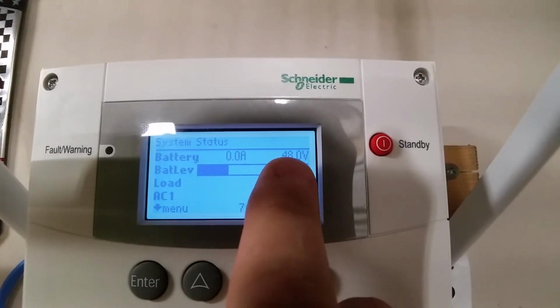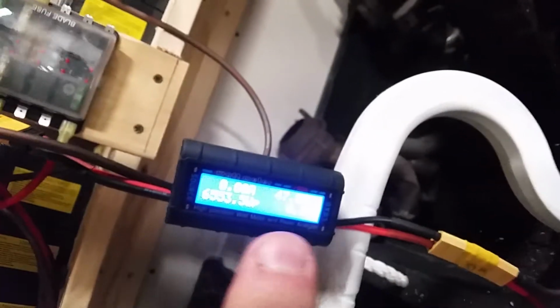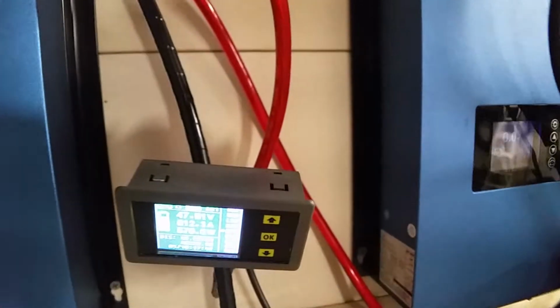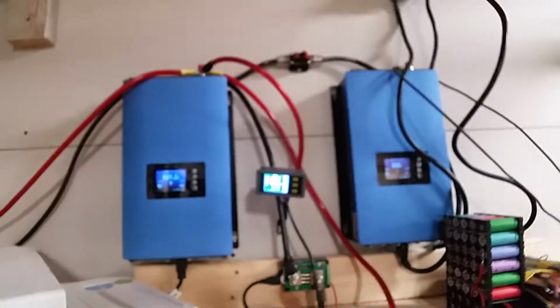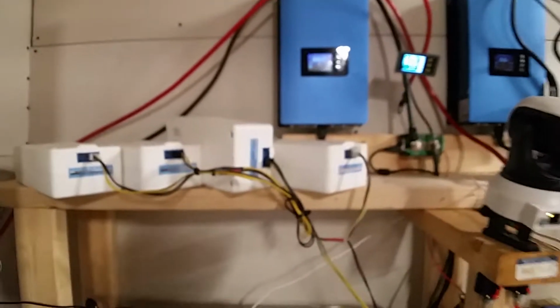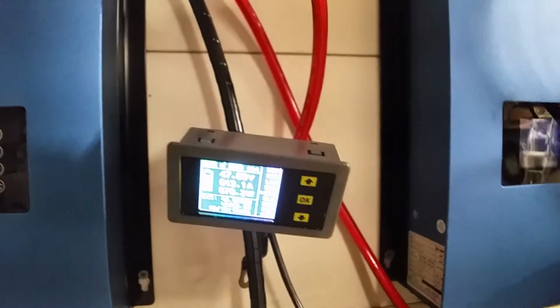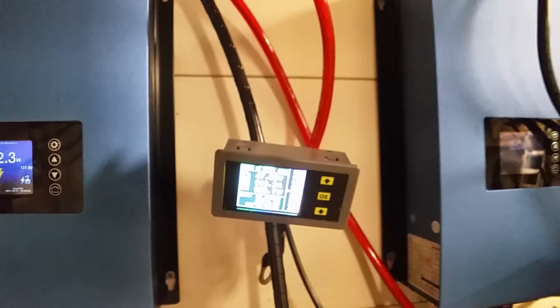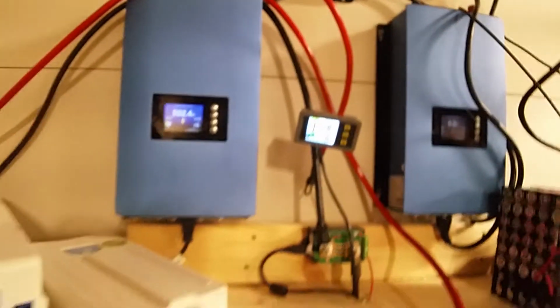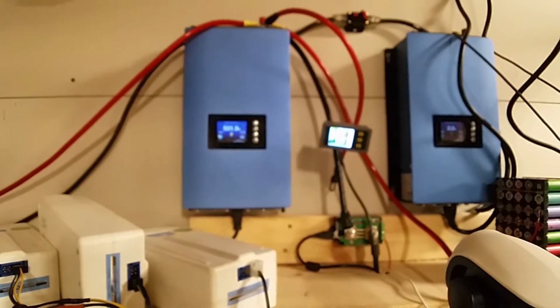This voltage, the problem is I don't know which one's right. This one shows 48 volts, this one shows 47.89, that one shows 47.81, that shows 48. If I put my actual fluke meter on there, it's in between those two and that one, so they're all roughly close. I'm going off this one a little more, I think it's accurate. So I'm actually not even getting my batteries up to the full 50.4, I think I'm only hitting like 49.9.